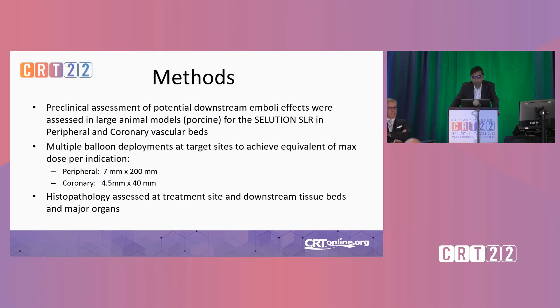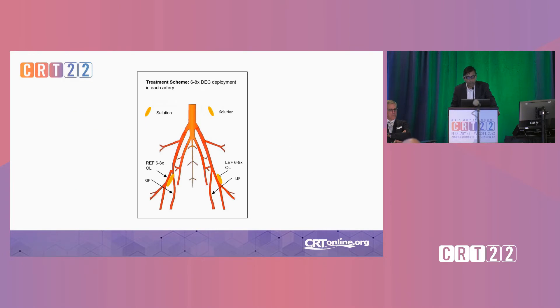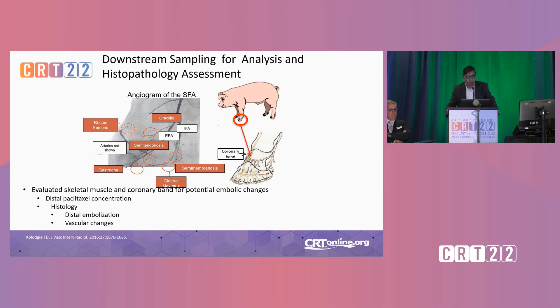Now for methods — we did a preclinical assessment of potential downstream emboli after the SELUTION SLR in both the peripheral and coronary vascular beds in a porcine model, with multiple balloon deployments at target sites to achieve an equivalent of maximum dose per indication. For peripheral, that was a 7mm by 200mm balloon, and for coronary a 4.5mm by 40mm balloon. We then assessed histopathology of the treatment site and downstream tissue beds in major organs. The study schematic shows overlapping multiple balloon deployments in the peripheral SFA model and also in the coronary, where we collect downstream muscle beds to look for embolic or vascular changes.